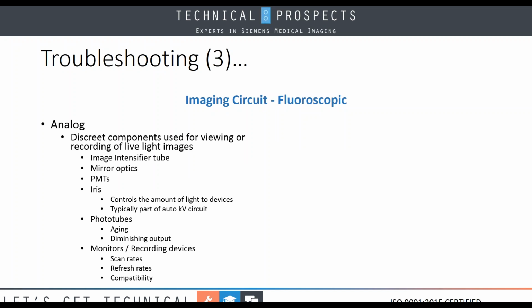When we look at the fluoroscopic circuit, let's start with the analog side. You've got a lot more components. First off, you've got your image intensifier tube. Is it properly functioning? You have the mirror optics, which is going to direct the output light somewhere. You have your photomultiplier tube. That's going to be in between the output of the image intensifier and whatever recording device we're going to be using, because that's going to be monitoring the light. And that's going to help set up and trigger our auto KV circuit. The iris going to our photo tube. All right, this is controlling the amount based on the opening and closing of the iris. All right, the iris itself may or may not be part of the auto KV circuit, depending upon individual design.